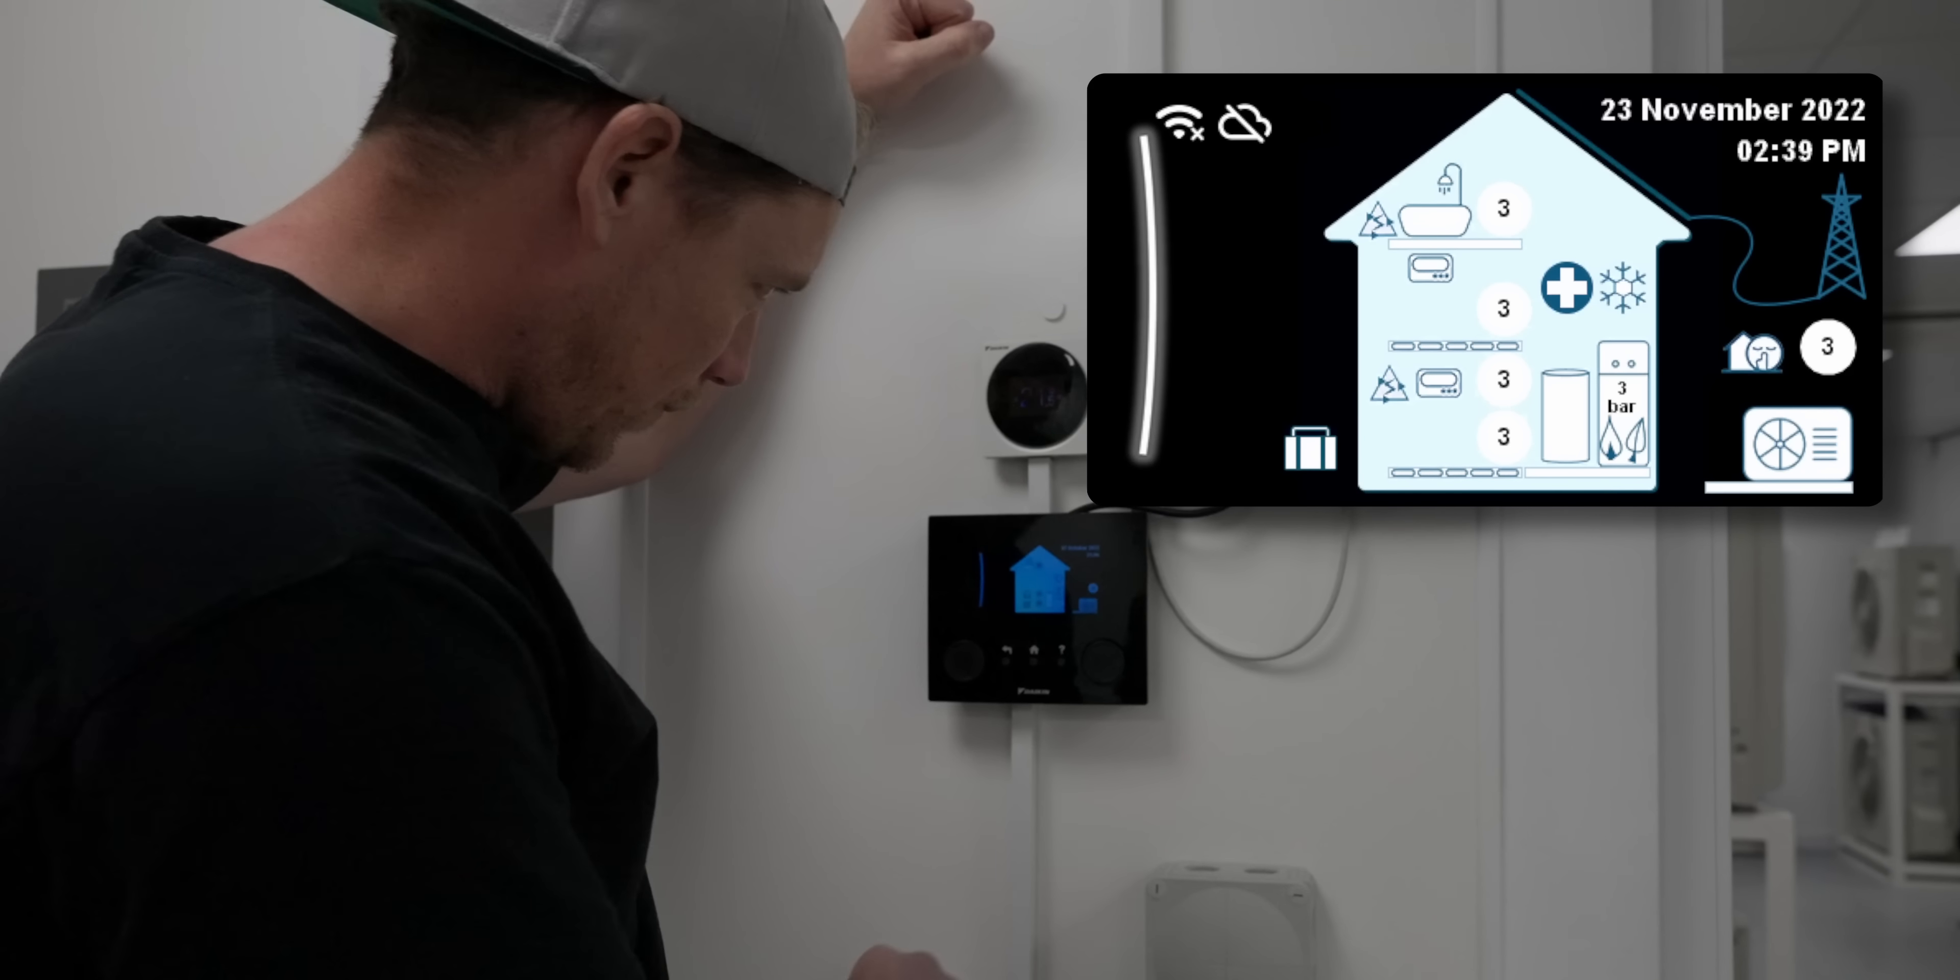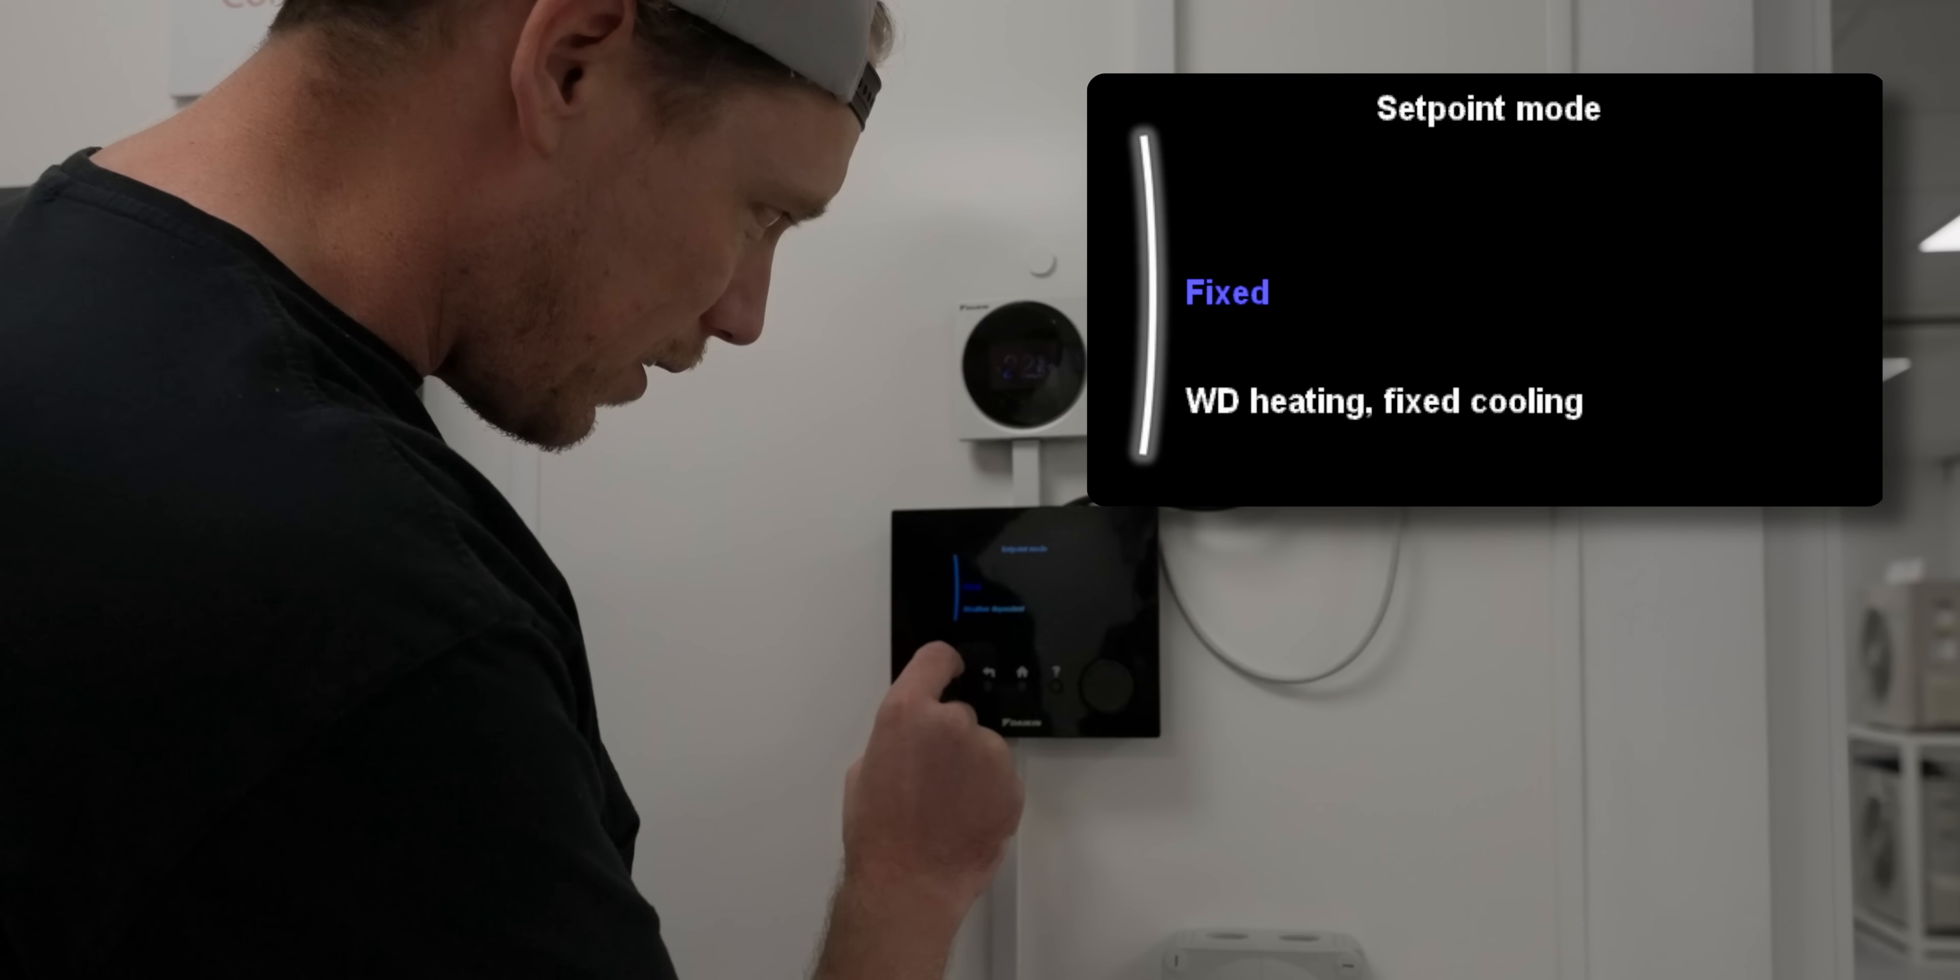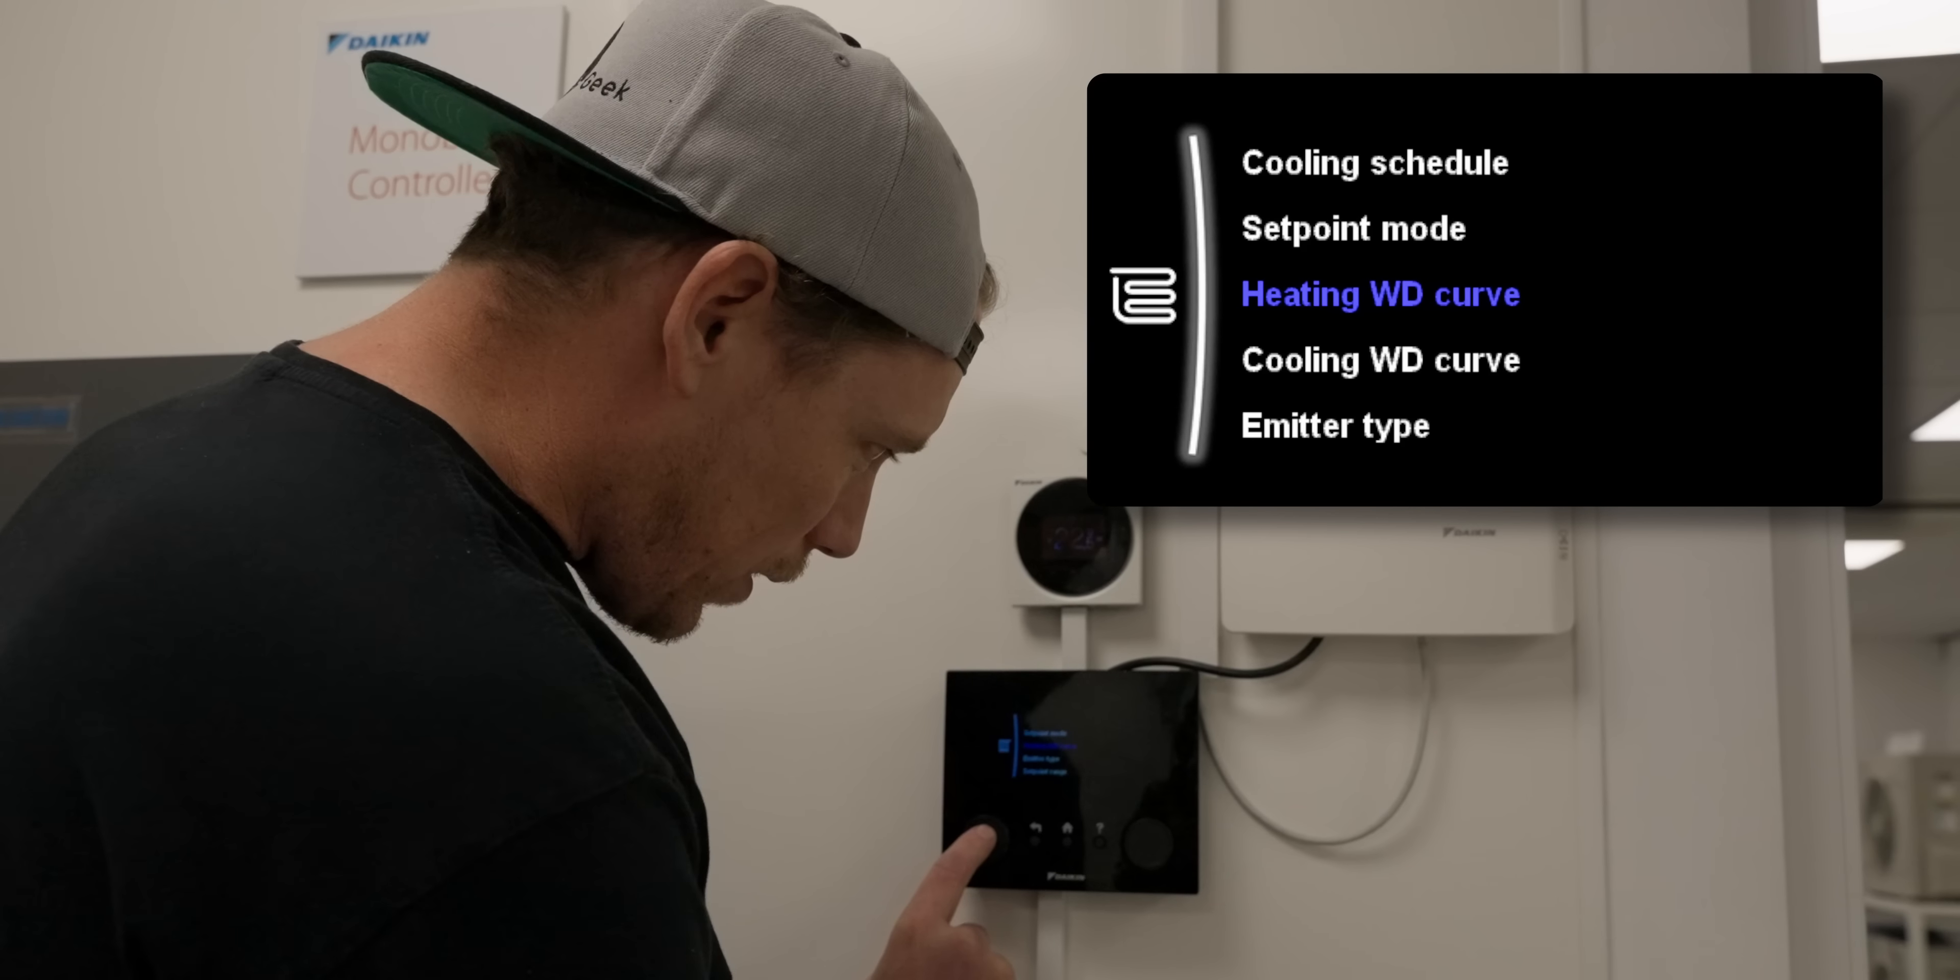From the home screen we're going to go in here, let's go down to main zone. Main zone set point mode fix the weather compensation. So if your Daikin is set to fixed, turn it off and put it on weather dependent. Fix just means it's fixed flow temperature which we don't want, we want weather compensation heating.